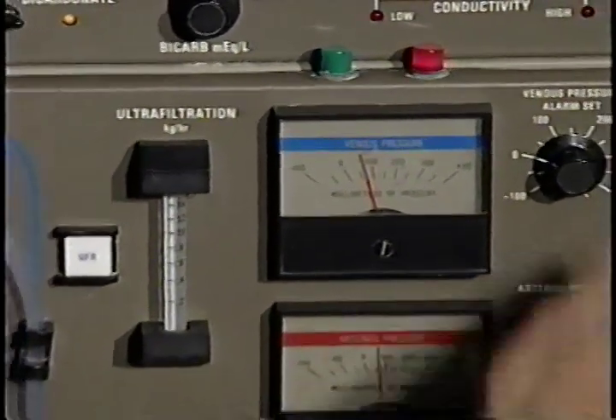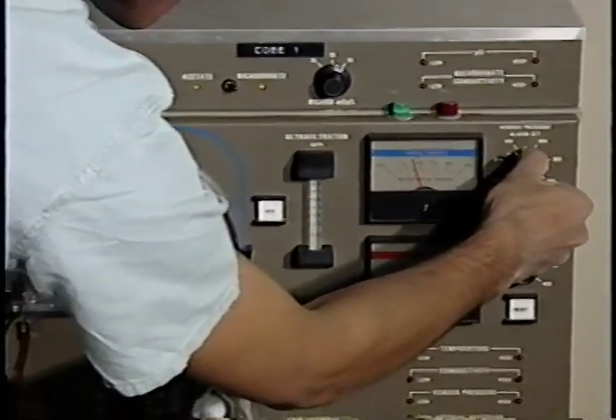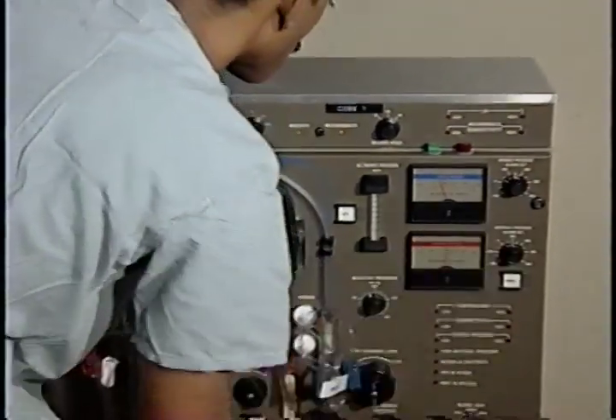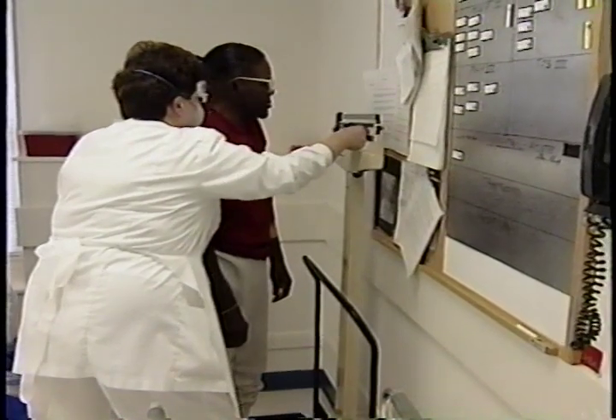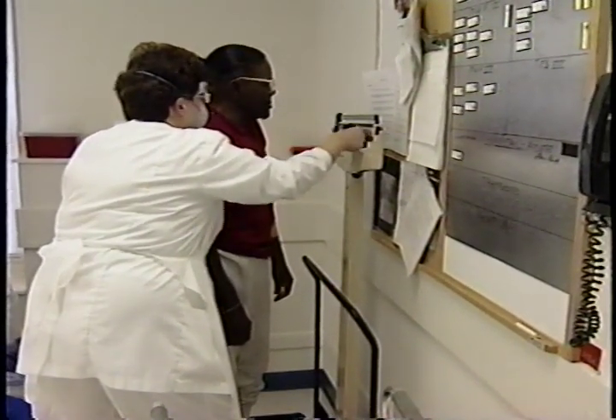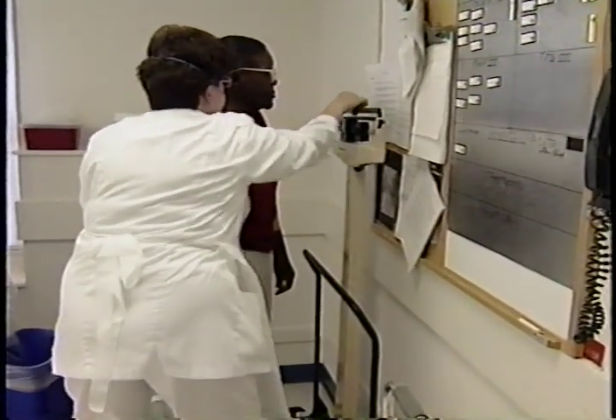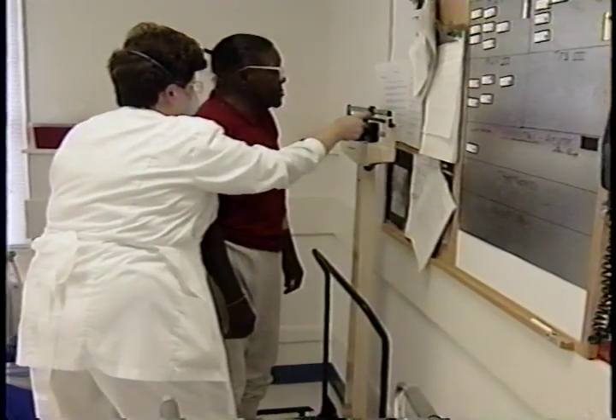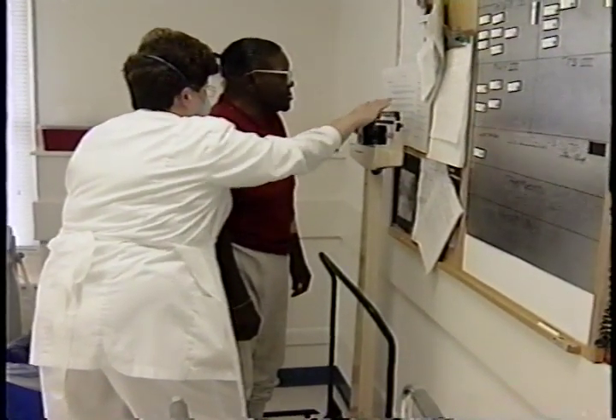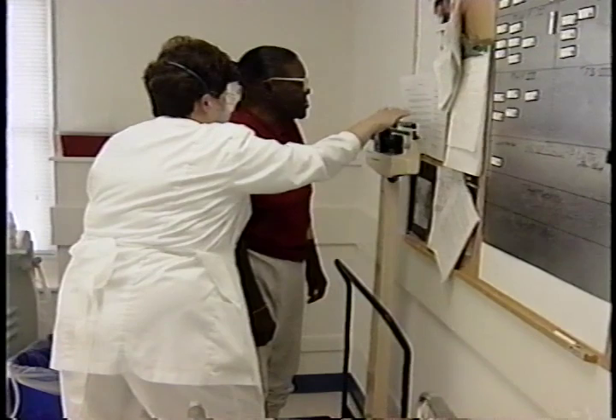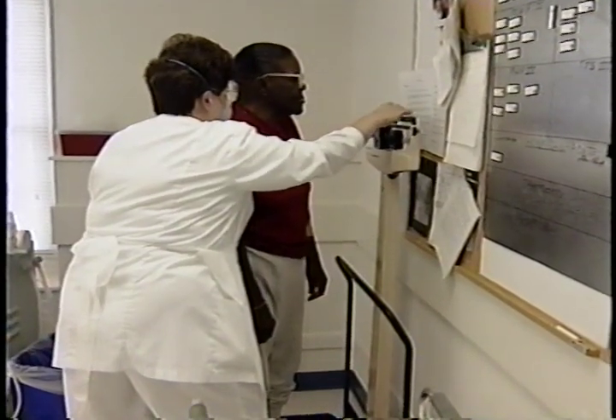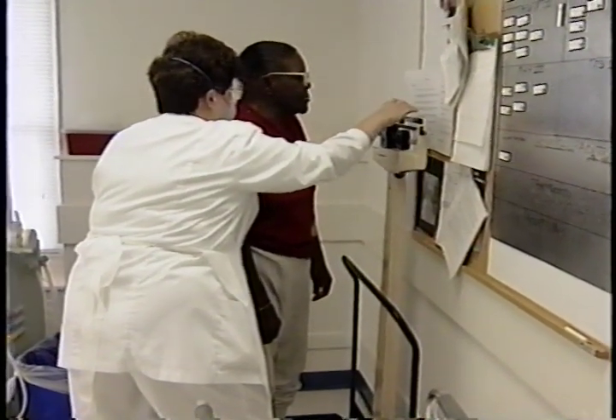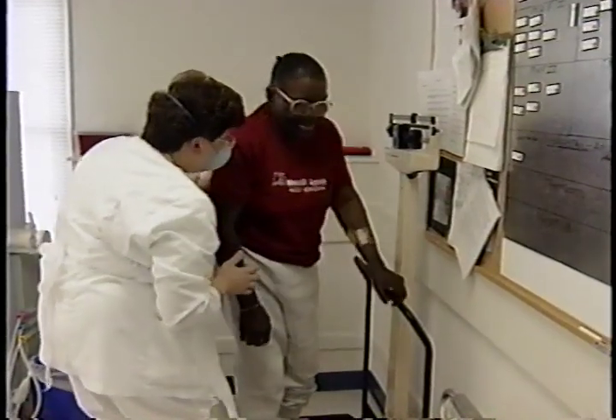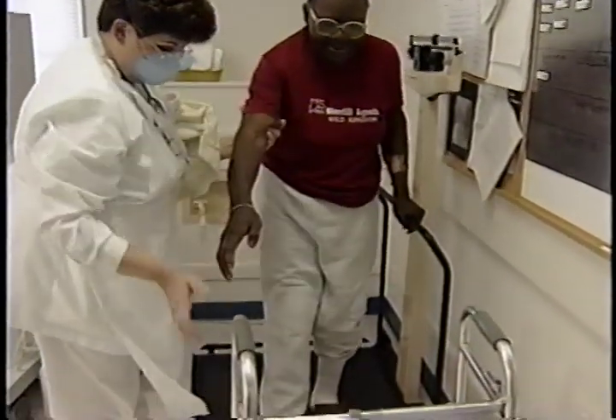Routine equipment safety checks should be performed before every treatment according to the manufacturer's instructions. Your facility's quality assurance should make certain that target weight losses are achieved. This includes a determination that the scales are properly calibrated, that TMP or negative pressure are correctly calculated, that ultrafiltration controls are functioning, and that the staff receives training in fluid management.